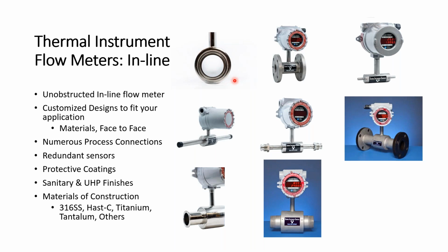The other nice benefit about looking at our units is you can see that because there's nothing inside the tube, as long as we are mating up to your process piping, you're going to see very negligible pressure loss, which is great if you've got pumps or different things downstream of this. You don't want to see any pressure drop going through a flow meter. So that's one of the advantages of being unobstructed. And then the other nice thing about our units is you'll see a variety of connections here. We've got welded ends here. We have tri-clamp, there's flange. We can give you threaded ends with VCO, VCR. We can give you NPT pipe, tube ends, you see it.